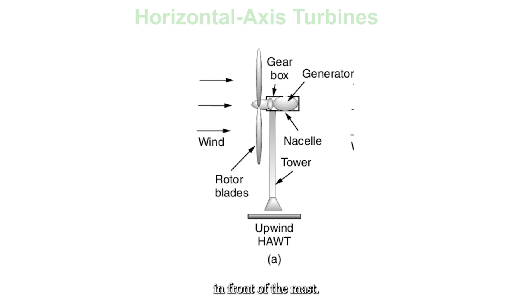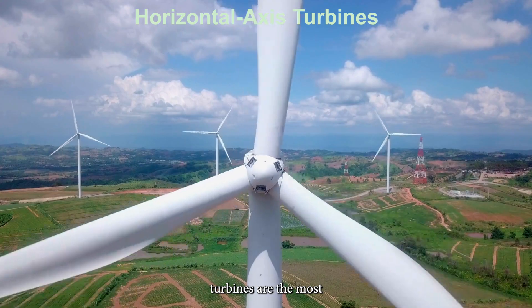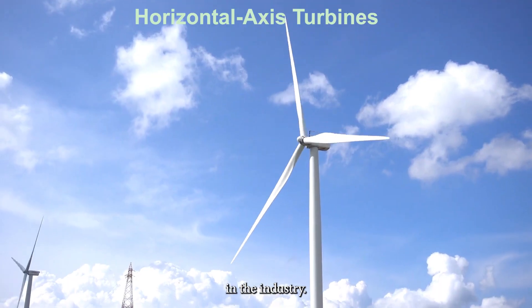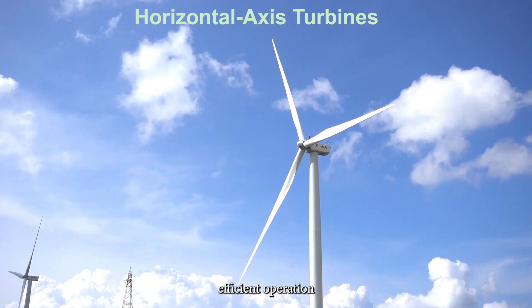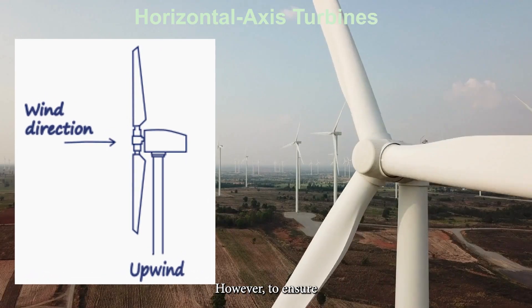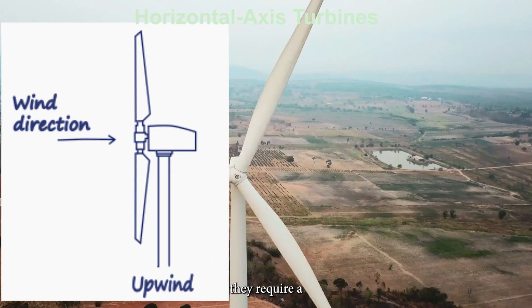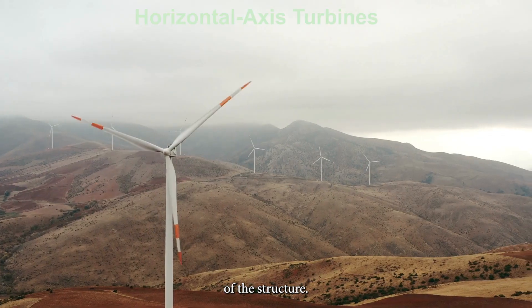Let's start with upwind horizontal axis turbines. These turbines face the wind, with the rotor blades in front of the mast. Upwind horizontal axis turbines are the most commonly used wind turbines in the industry. They offer efficient operation and are less susceptible to wear and tear. However, to ensure proper alignment with the wind, they require a yawing mechanism, which adds to the overall weight of the structure.